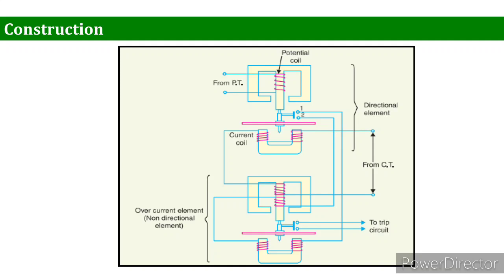Looking at construction, this is an induction type directional overcurrent relay. A typical induction type directional overcurrent relay basically consists of two relay elements — one is the directional element and the other is the non-directional element, also called the overcurrent unit. There are potential coils for the directional element and on the bottom an overcurrent element. These two elements combined form the directional overcurrent relay.